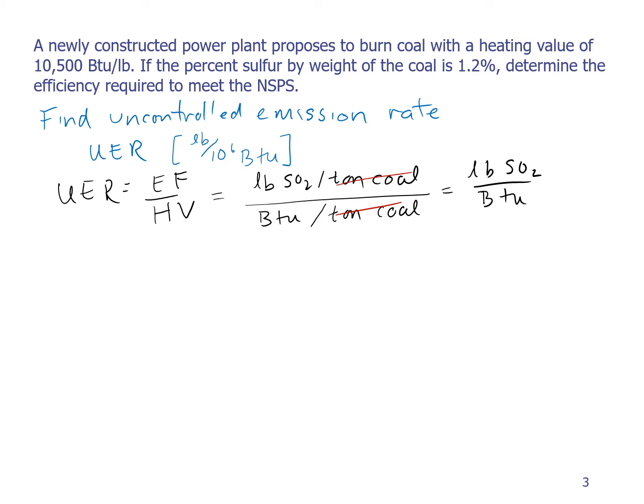So the emission factor here is 39S, as we discussed, and that's 39 times 1.2, and you use 1.2, not 0.012, and that gives me 46.8 pounds of SO2 per ton of coal.